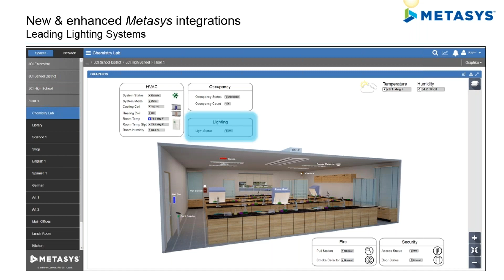Instead of serving up individual BACnet points per lamp, they now organize their lighting data as lighting zones or groups and represent those as virtual BACnet devices, so they don't overwhelm Metasys or even other third-party building automation systems with loads of unorganized data.